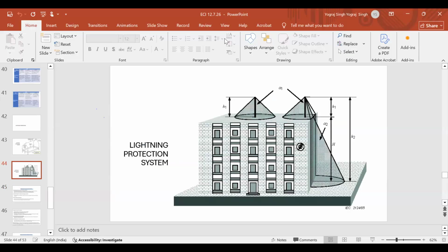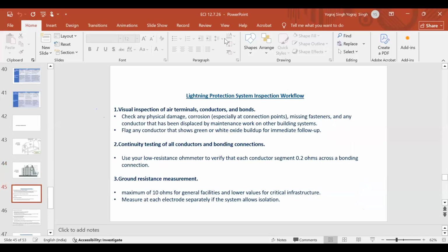the energy should be taken into the ground in the fastest possible time. The thing is, this is massive energy, lakhs of volts and very strong heat, so wherever it finds any resistance, it will convert into heat, and it will burn that area. So earth is a good conductor, so every energy should be allowed to be dissipated into the earth. Here the efficacy of that earth electrode is very important, which I had shown in previous slides.